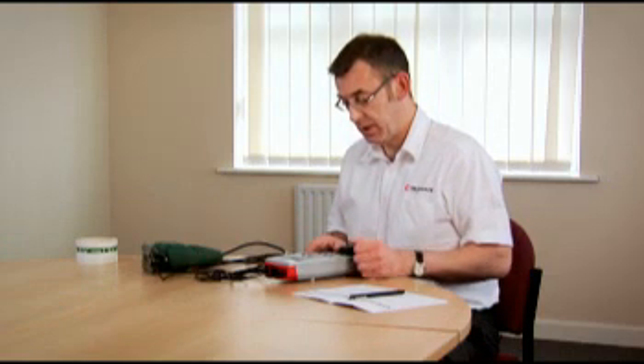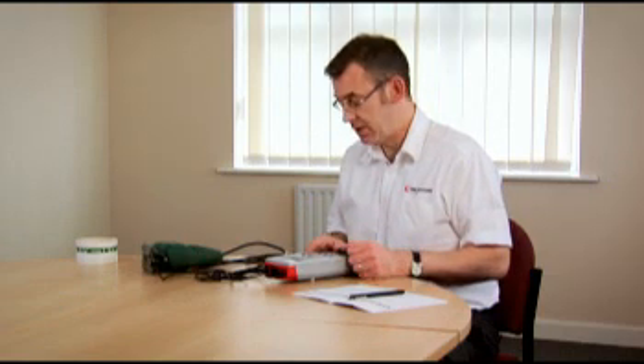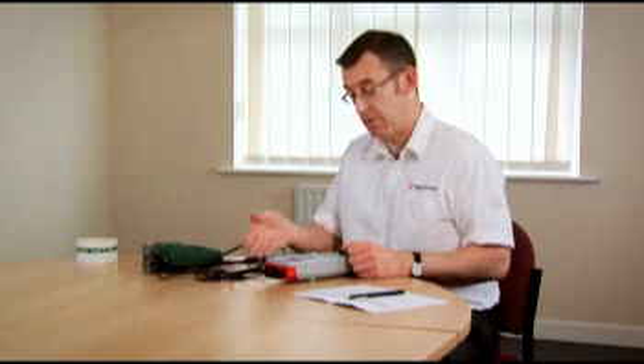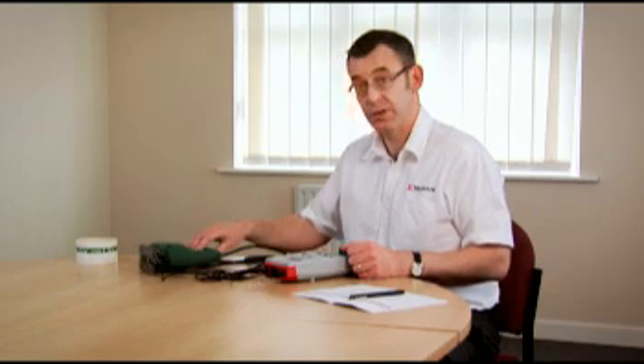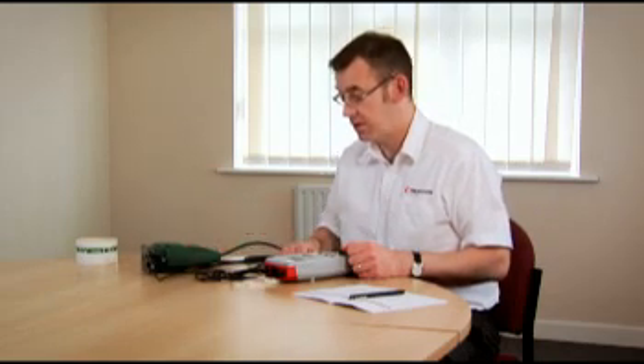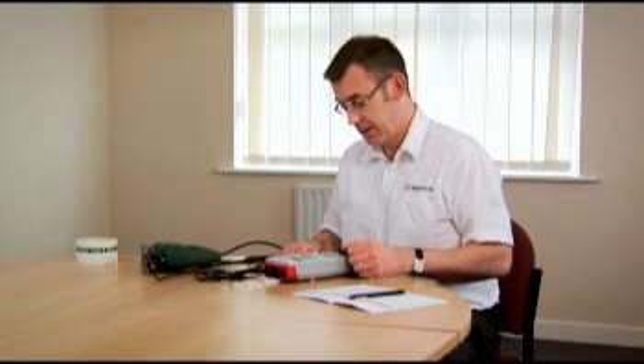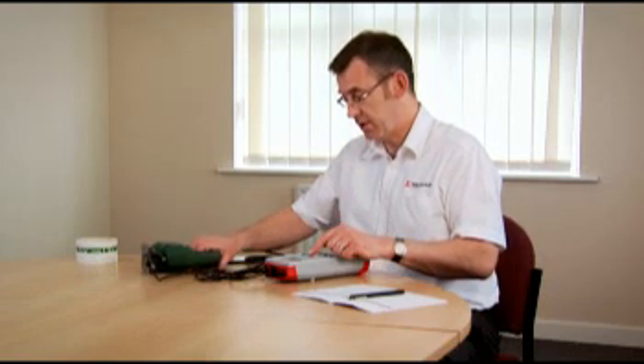Now, before we start the sequence, we need to remember that it is going to power the appliance because we've got mains coming in, so we need to make sure it's safe to do so. So you'll note there's no blade in the saw. Switch the appliance on. Push the test key.